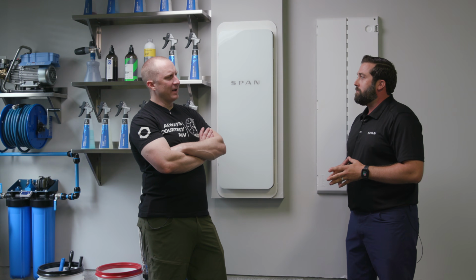And that's with any third-party EV charger. Span does have our own EV charger coming out hopefully later next month, and instead of pausing that load, we can actually dynamically shed it. So let's say you have a full 48 amp charge going on, but an electrical appliance comes on that exceeds the capacity of the panel. If that load only leaves us with 40 or 30 amps, we will dynamically shed down to 30, 40, 25 amps, whereas with a third-party EV charger, we just pause that load until the other appliances go off.